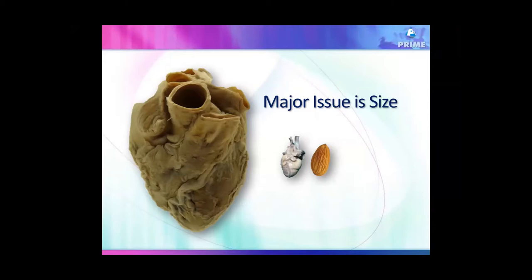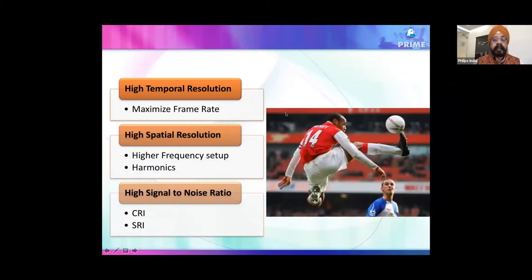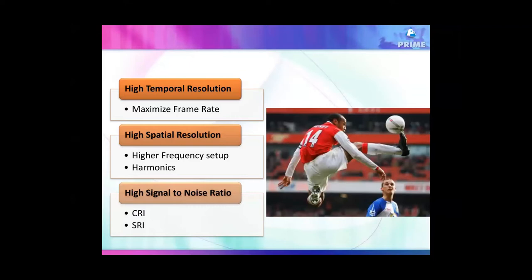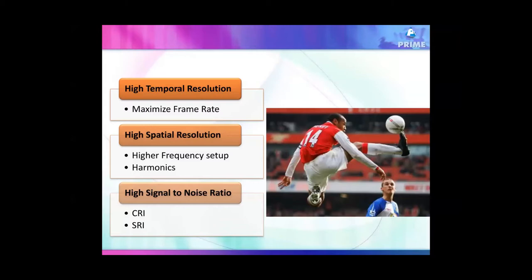This presented challenges to equipment, especially 10 years ago when I started. You needed very high temporal resolution because the fetal heart moves at 140–150 bpm — the normal average rate is 110–160. You also needed very high spatial resolution because structures were tiny and you needed to differentiate millimeter from millimeter, while keeping the noise ratio appropriate.